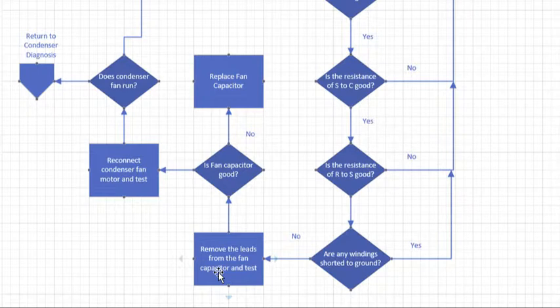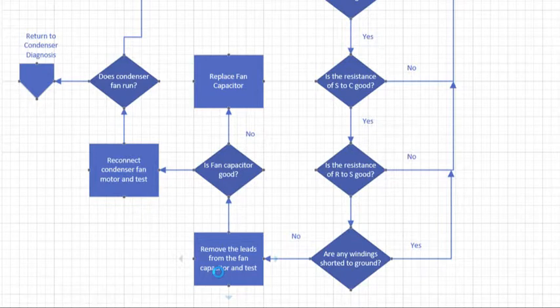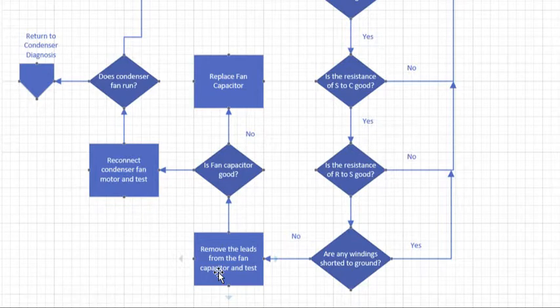Remove the leads from the capacitor and test the capacitor. Realize that a lot of these capacitors are combo capacitors. You're going to have some leads going to the compressor and some leads going to the fan. You have to remove both start leads or you're going to have a problem because you'll have two capacitors in parallel with each other. Is the fan capacitor good? If it's within 10% of your rating or sometimes 5%, depending on what the tolerance is on the capacitor, it's good. If it's outside of that, it's not good.